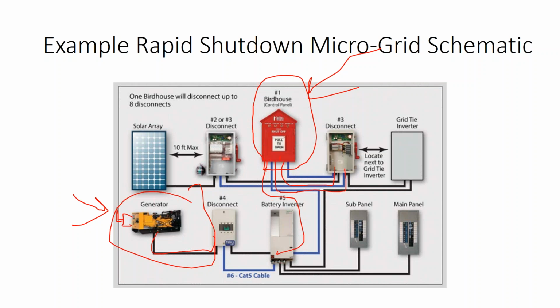And I'm not so sure that that's the best idea, because if you locate a system level shutdown outside the building, to me that can invite more opportunity for pranksters to turn your building off than the fire department to get much use out of it. But then again, you have to be able to give the fire department a way to turn off your backup system. So the best way to do that is not really well defined in code at this time.